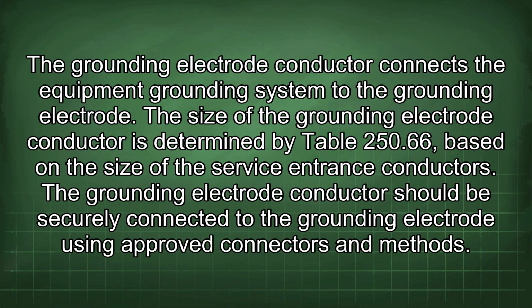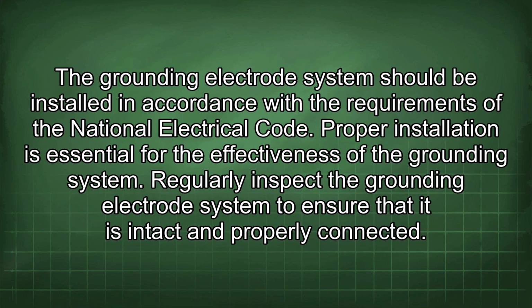The grounding electrode conductor connects the equipment grounding system to the grounding electrode. The size of the grounding electrode conductor is determined by Table 250.66, based on the size of the service entrance conductors. The grounding electrode conductor should be securely connected to the grounding electrode using approved connectors and methods. The grounding electrode system should be installed in accordance with the requirements of the National Electrical Code. Proper installation is essential for the effectiveness of the grounding system.